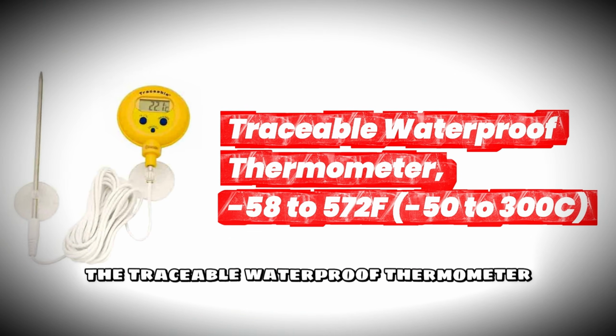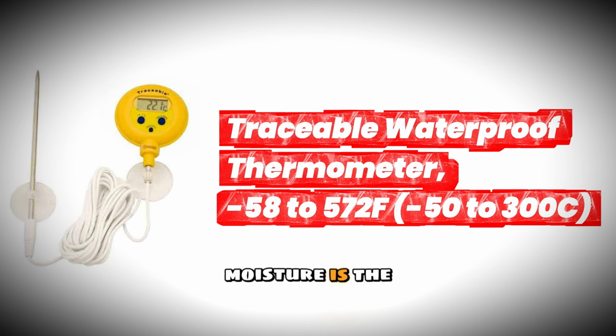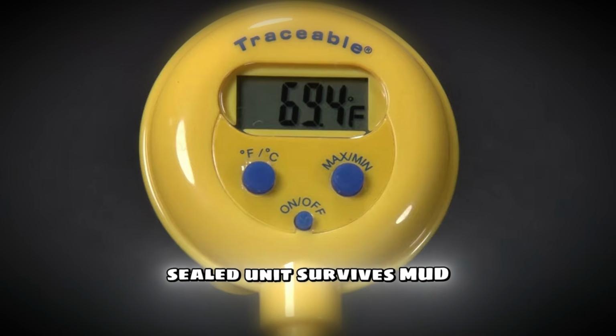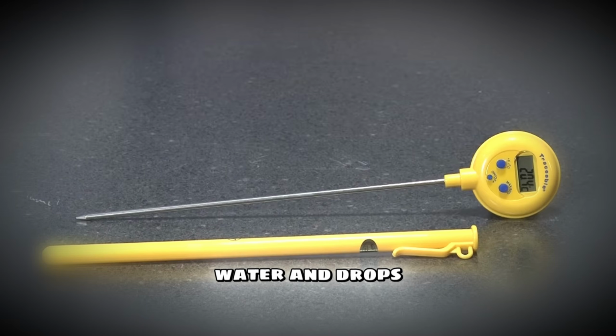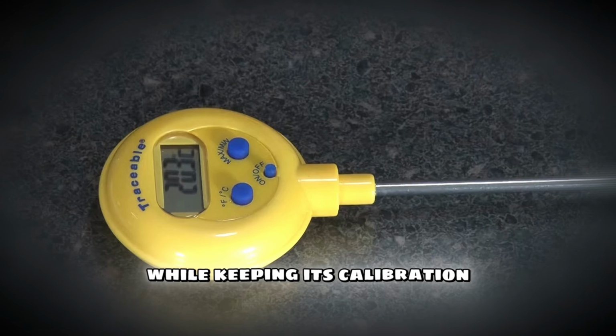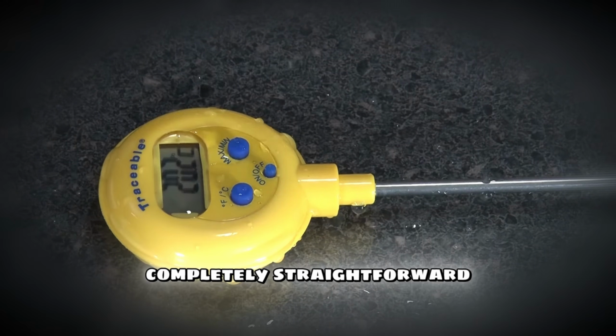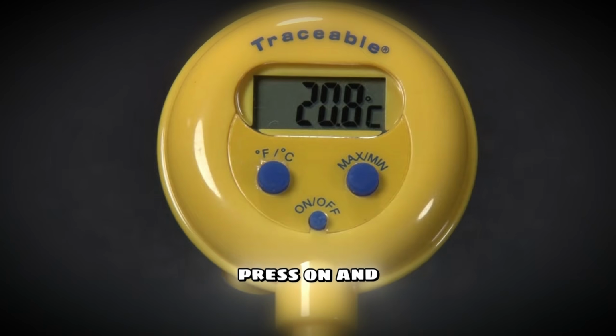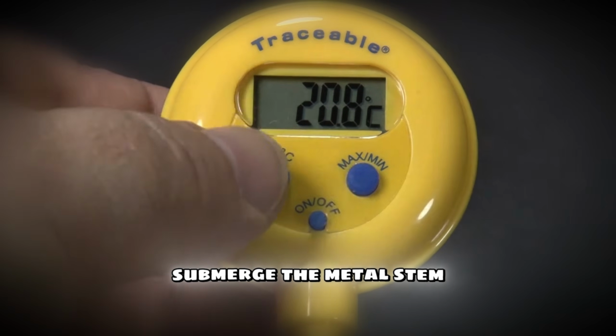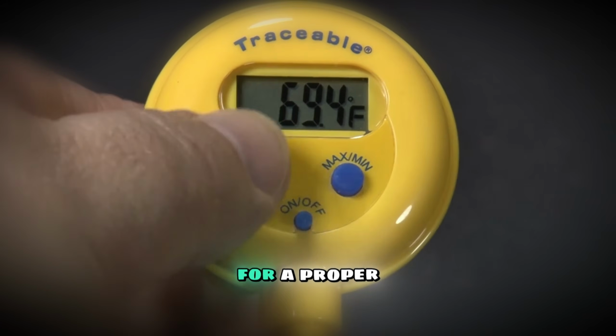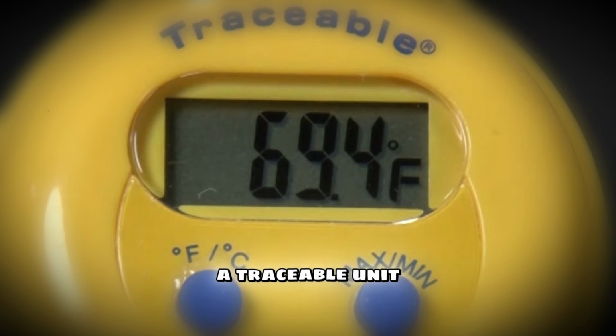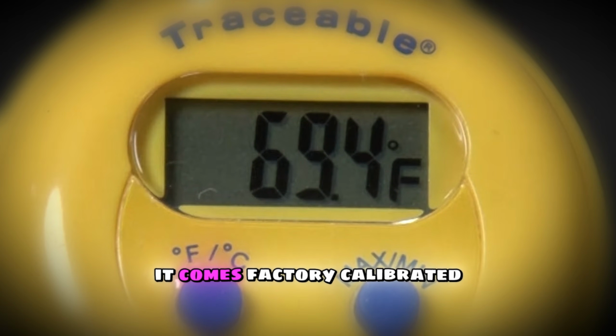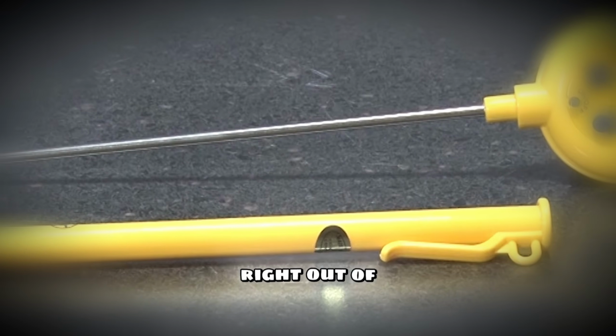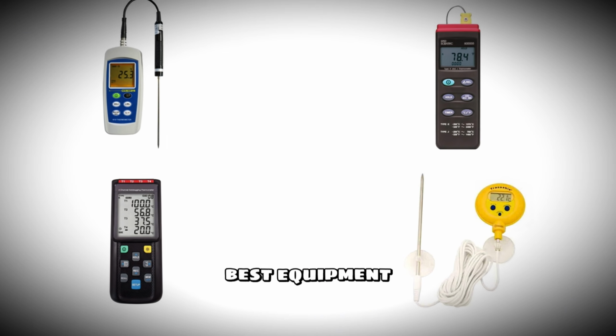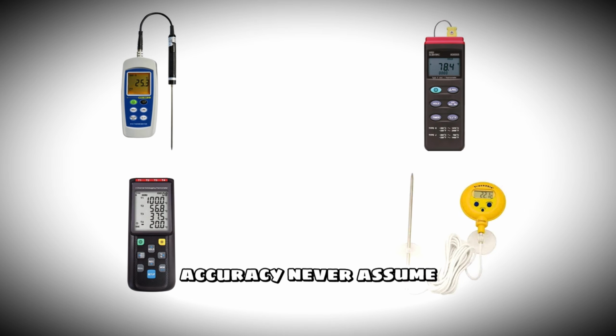Finally, we have the traceable waterproof thermometer. Moisture is the enemy in the field, but this fully sealed unit survives mud, water, and drops while keeping its calibration. How to use it? It is completely straightforward. Remove the sheath, press on, and submerge the metal stem at least 1 inch into your sample for a proper core reading. Because it is a traceable unit, it comes factory calibrated and is completely ready to trust right out of the box.